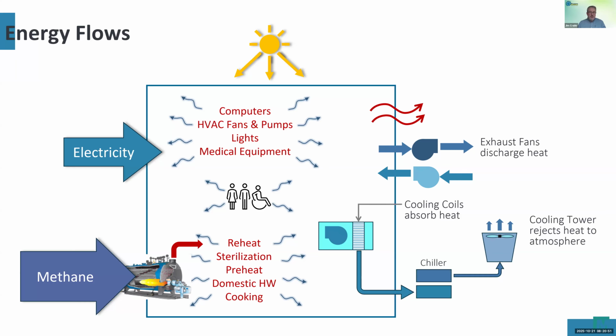And so our cooling system is designed to absorb all that heat. We run our chill water and our air handlers. The air handler transfers heat from the air to the chill water, the chill water goes to the chiller, which transforms the energy to a higher temperature and takes it to the cooling tower, where the cooling tower throws it away.